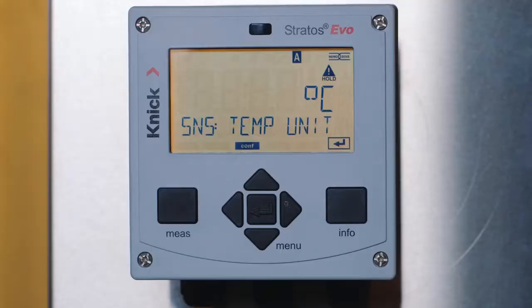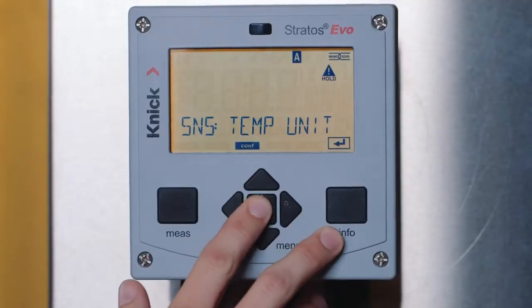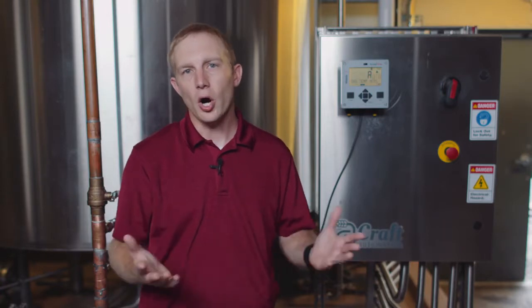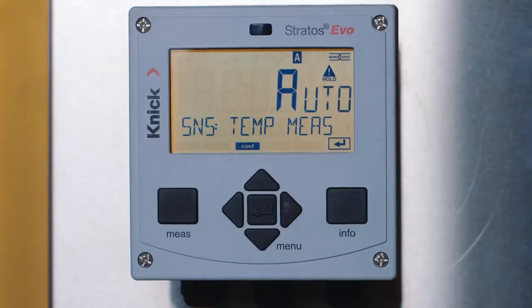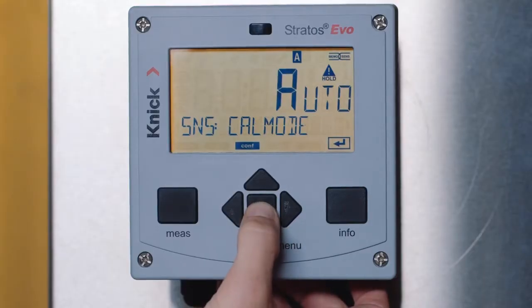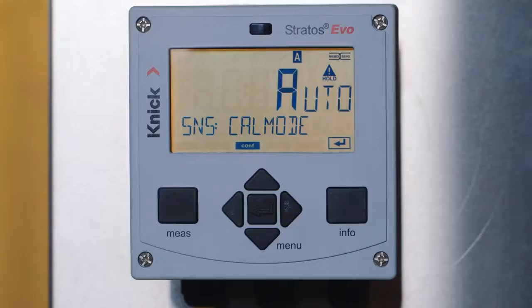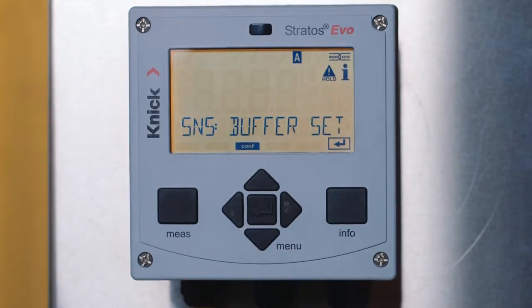The next parameter is the setting for temperature display. We will select Fahrenheit and press enter. This is followed by the type of temperature measurement, automatic or manual, along with the temperature calibration method. We will select auto for both to ensure that temperature is automatically compensated when making the measurement. Next, we see the calibration mode for our pH sensor. We recommend auto, which provides automatic buffer recognition and temperature compensation of the buffers.